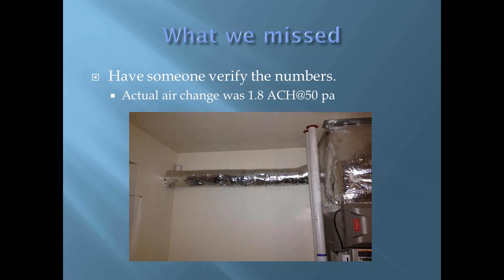And so how many CFMs do you think you're getting with this? The 6-inch would flow with just the furnace running about 70. If I had all the other exhaust on it, I could get it up to a little bit over 80. But I've tested this on another house that had a 600 CFM range hood. It would only pull 80. So it has a self-limiting factor to it. And the negative pressures were substantially different between the two houses, and it still pulled 80. So I tested it under a whole bunch of different static pressures to see if it would change it, and it doesn't. So, yes, sir.